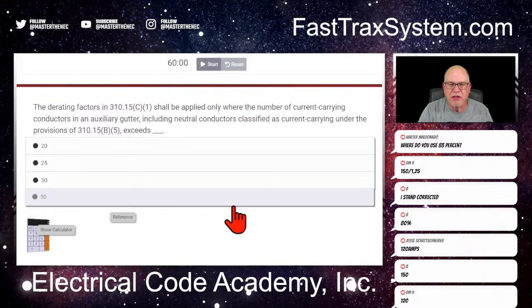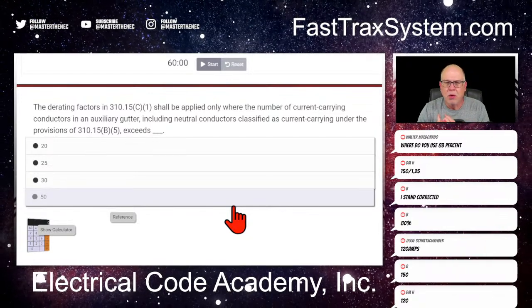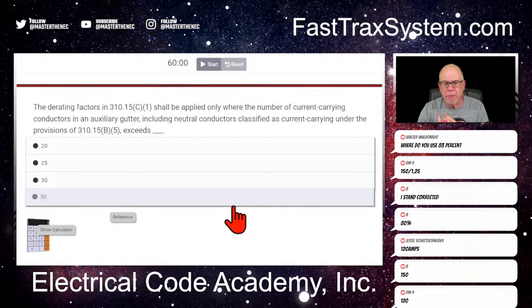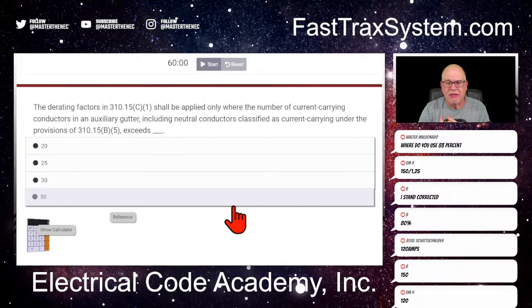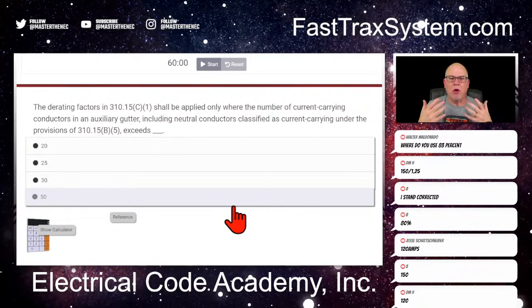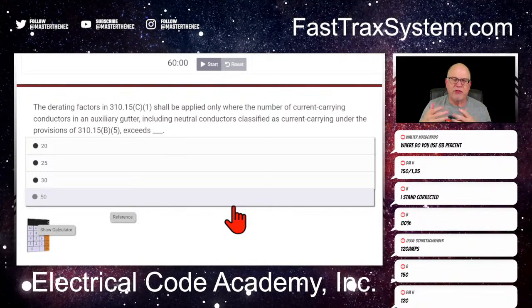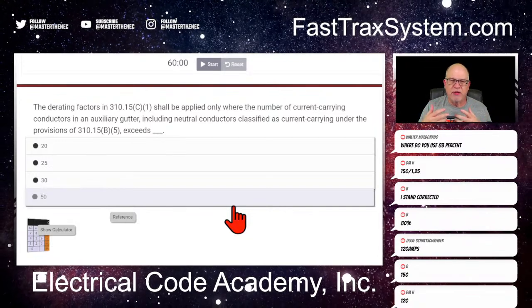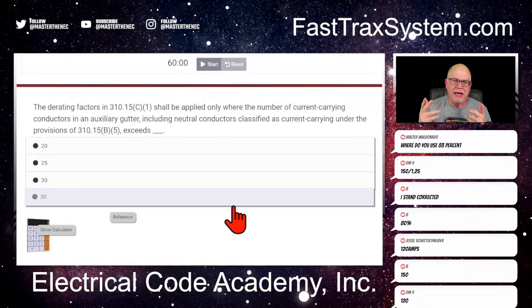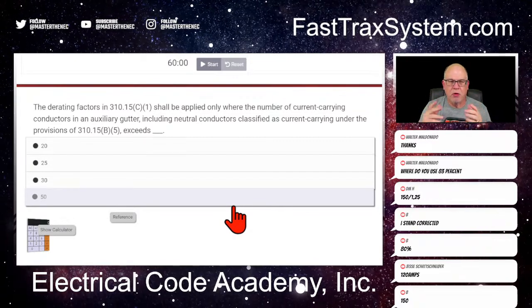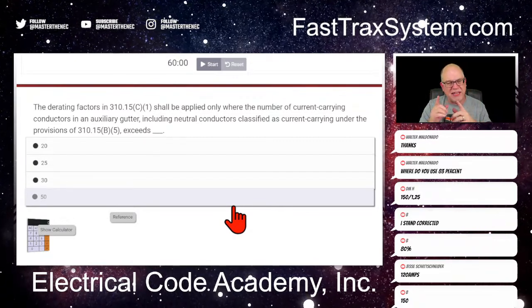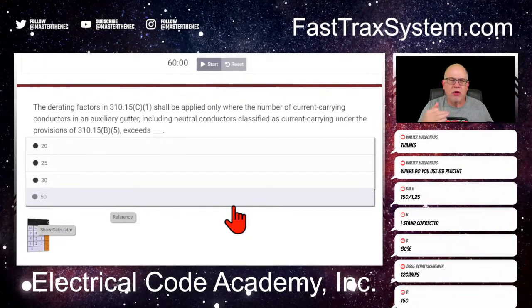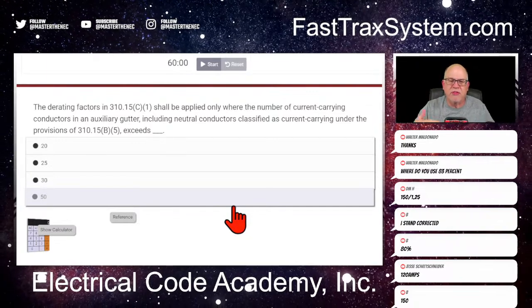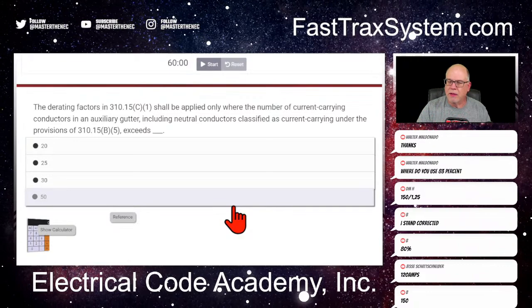Think of 83% when you're going to apply 310.12. And remember the rules, Walter, in 310.12, it's only for service. There was nothing in that question about a service. The 83%, it has to be between 100 and 400 amps, right? So again, it's got all those nuances, but that's 310.12. We were just talking about a simple overcurrent device and its limitation, okay?